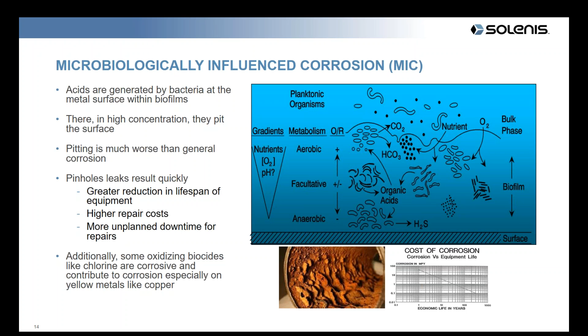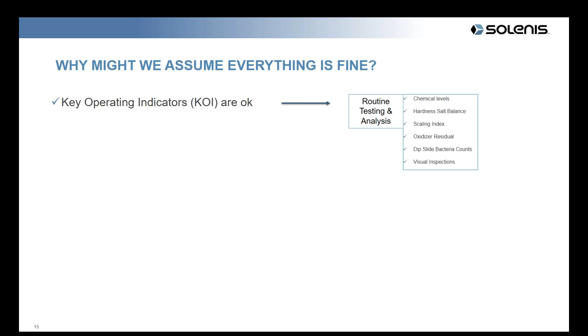So how do we get into this thought of everything's fine, we don't really need to do anything about it, that Bob talked about? Well, we've got key operating indicators that we monitor, your routine testing. We check the chemical levels, we check the balance of the hardness, we check the scaling index, we check the residuals on the oxidizers and our bacteria counts, and we look at it, and so everything's fine. So that kind of gives us a false sense of security.